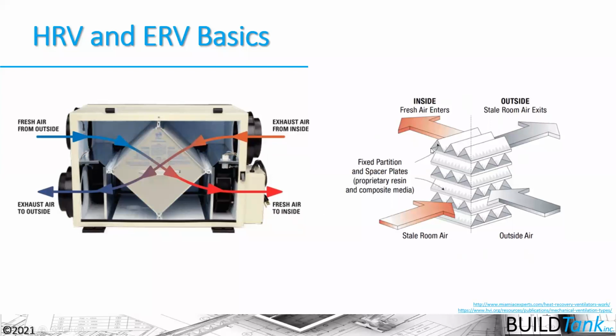So for the core, think of a cardboard corrugated box. If you look at the edge of that box, you'll see these little channels going through. The air moves through those channels, and those channels are oriented so that the airstreams don't physically cross or mix with each other, but they go through the core. And that core is made of a material that enables energy to transfer across from one airstream to the other, and potentially moisture to transfer across that core material, without the airstreams actually mixing together.